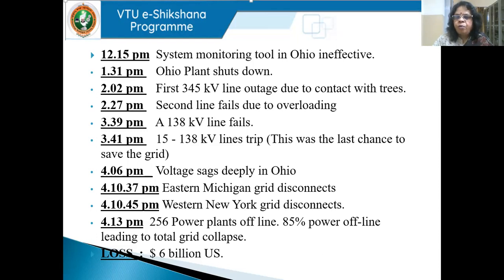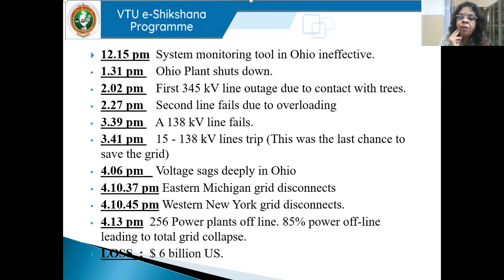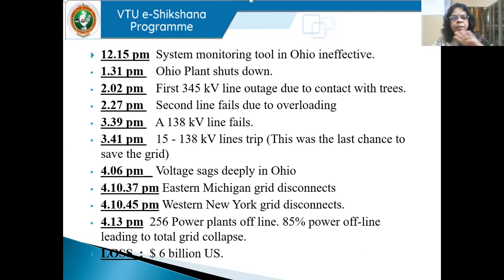About one hour and fifteen minutes later, at 1:31, the Ohio plant shut down. Then after another half hour, a 345 kV line got outaged — the line was opened due to contact with trees. This is very common with overhead lines, because trees have sap and are conducting bodies. During monsoon season, for example in Karnataka, trees are pruned to prevent inadvertent short circuits when it rains.